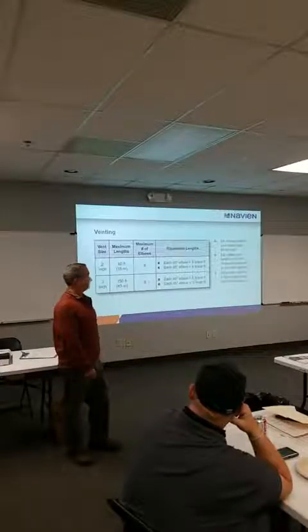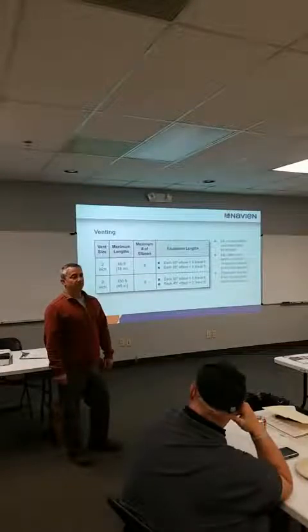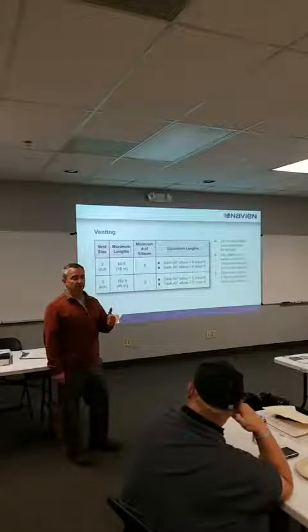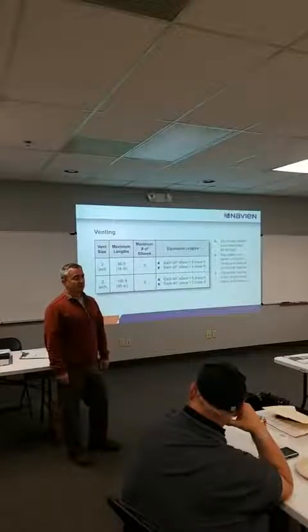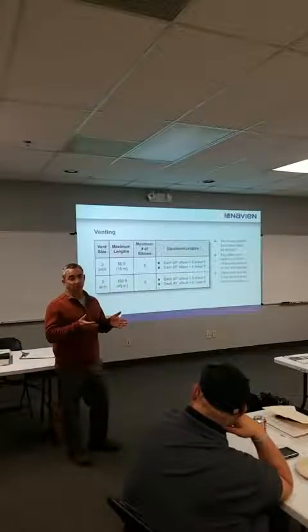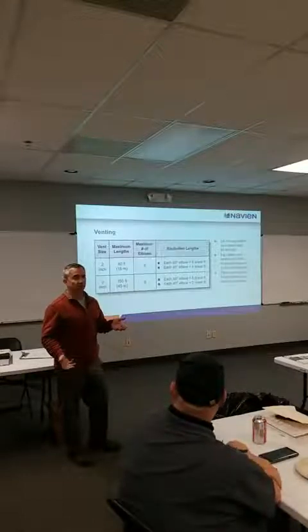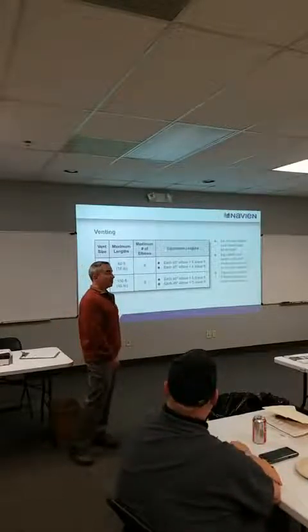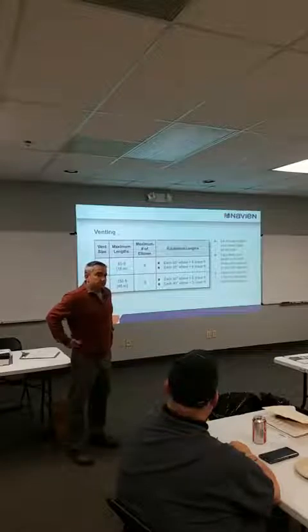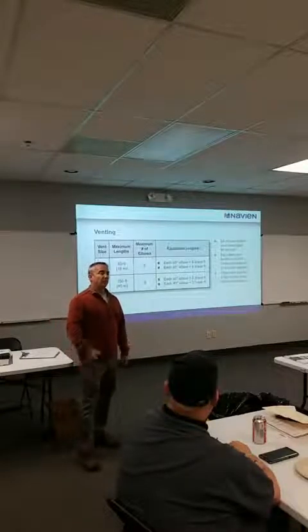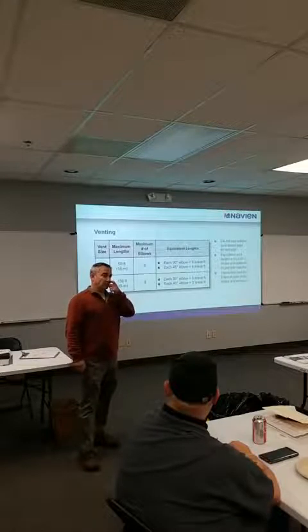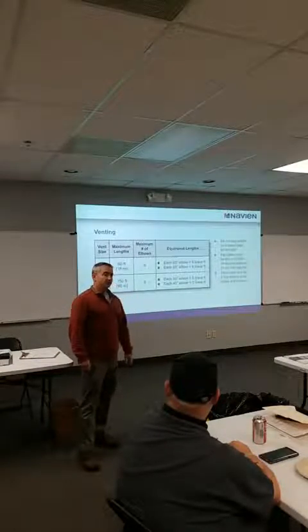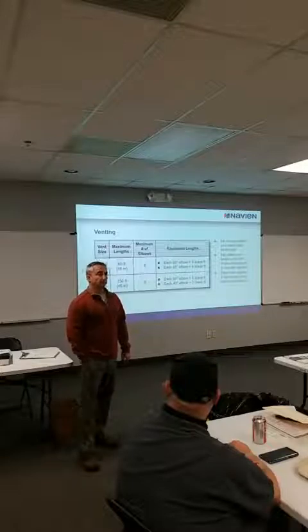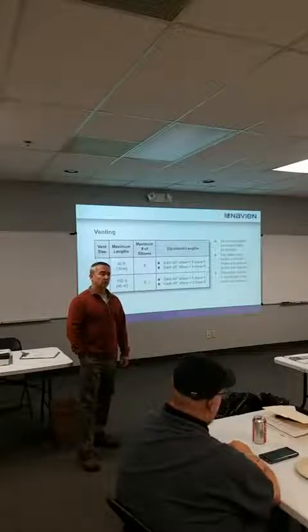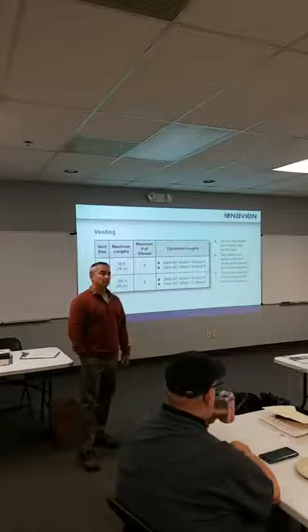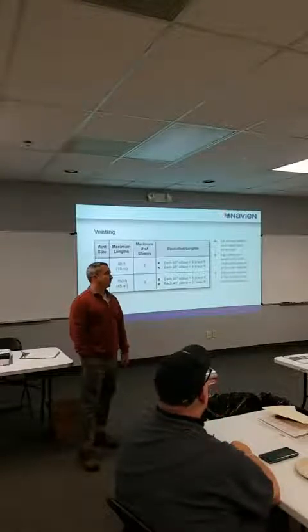How about brownouts is what I was thinking about. Yeah, if you have a power outage, it could mess it up. Lightning strike. They don't draw a lot of amps, but there's a computer board in there. So you could plug it into a surge protector, but it needs to be a decent one. Probably better off, if you're going to run it off a generator or something like that, maybe even investing in a UPS to clean it up. We've seen some issues with generators. Have you seen any of this equipment on UPSs like Terry said? I don't know what that is. Uninterruptible power supply, like they put on computers. It's a power conditioner.